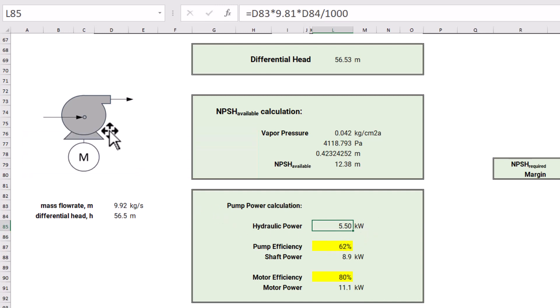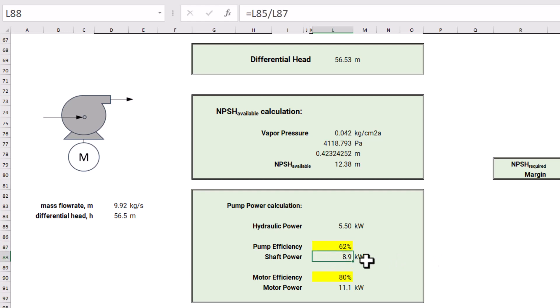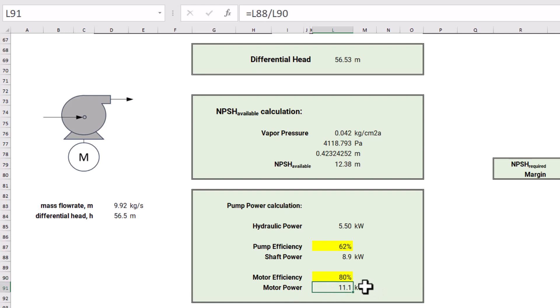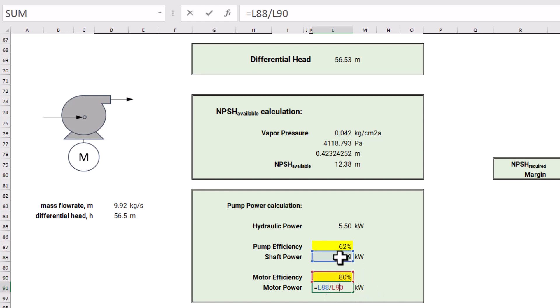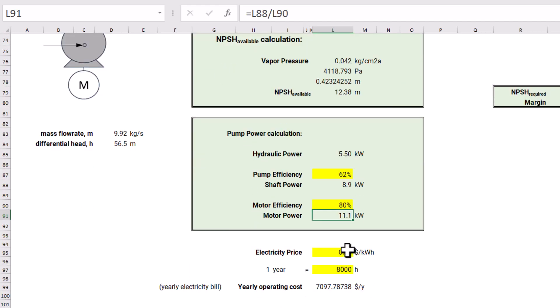Now let's say we have already selected a pump model, and its efficiency at this mass flow rate and differential head is around 62%. In that case the shaft power is 8.9 kilowatts, calculated by dividing the hydraulic power by the pump efficiency. For the motor, let's say it has been selected with an efficiency of 80%. The motor power then becomes 11.1 kilowatts, obtained by dividing shaft power by motor efficiency. This is the actual power consumed while running our pump.